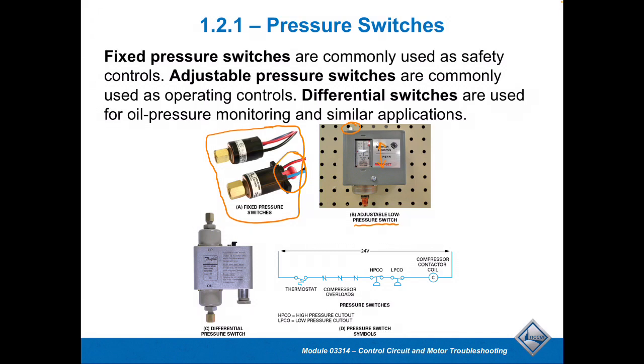They're not all the same. Whether you're setting up a Honeywell or a Penn or a Ranco control, or whatever the pressure switch controls might be, a Danfoss, you have to know and look at what you're looking at to make those adjustments.